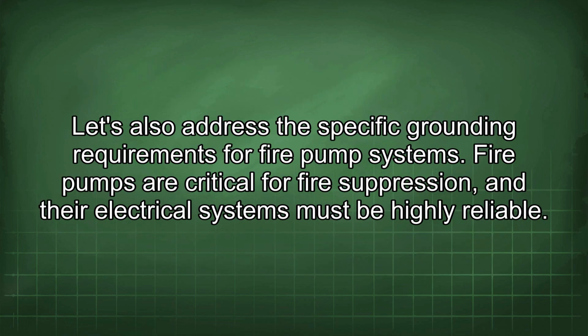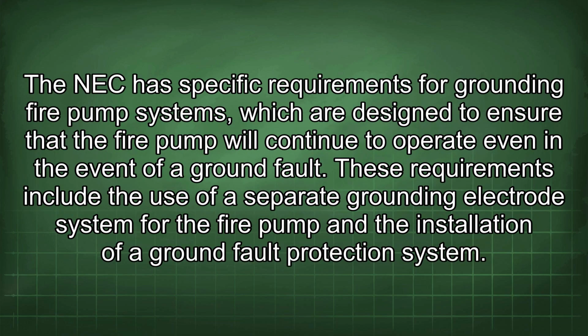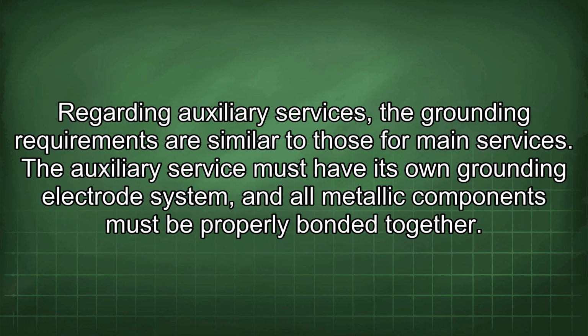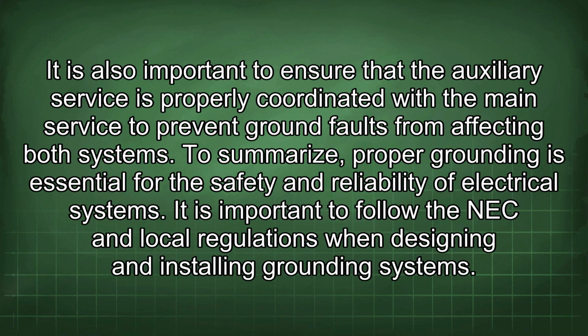Let's also address the specific grounding requirements for fire pump systems. Fire pumps are critical for fire suppression, and their electrical systems must be highly reliable. The NEC has specific requirements for grounding fire pump systems, which are designed to ensure that the fire pump will continue to operate even in the event of a ground fault. These requirements include the use of a separate grounding electrode system for the fire pump and the installation of a ground fault protection system. Regarding auxiliary services, the grounding requirements are similar to those for main services. The auxiliary service must have its own grounding electrode system, and all metallic components must be properly bonded together. It is also important to ensure that the auxiliary service is properly coordinated with the main service to prevent ground faults from affecting both systems.